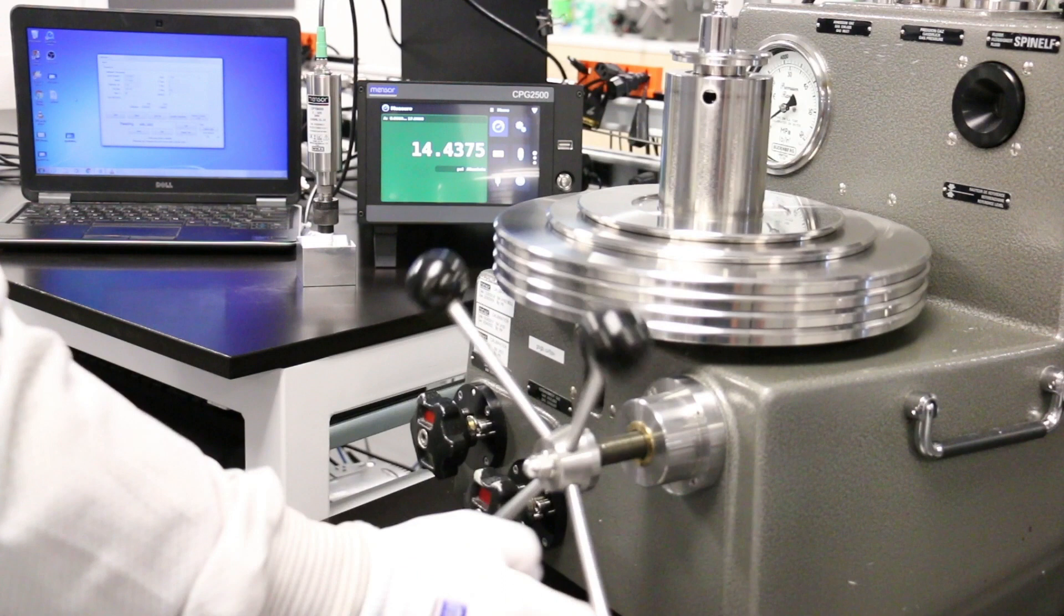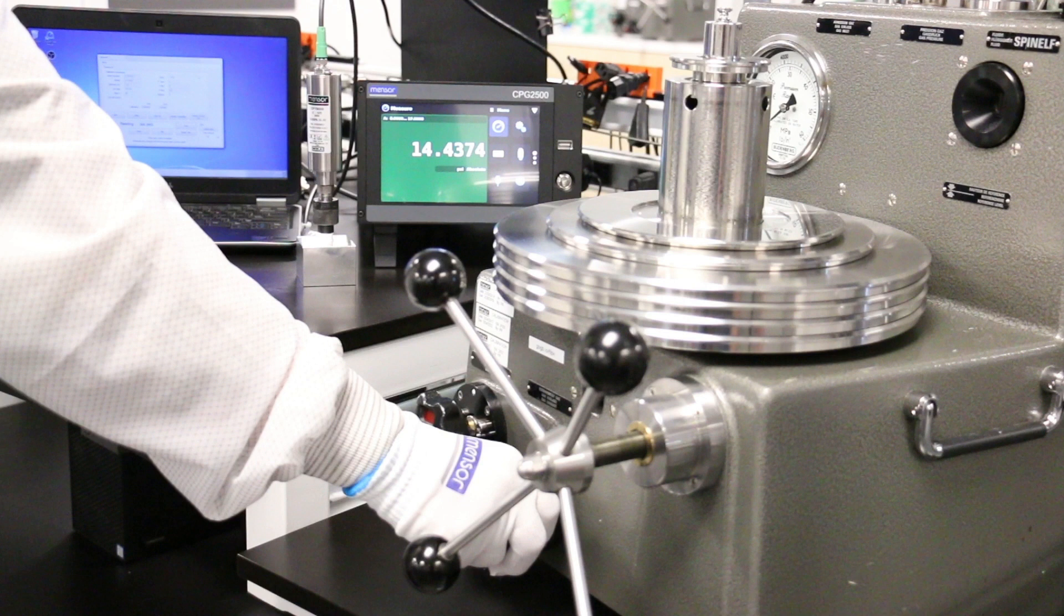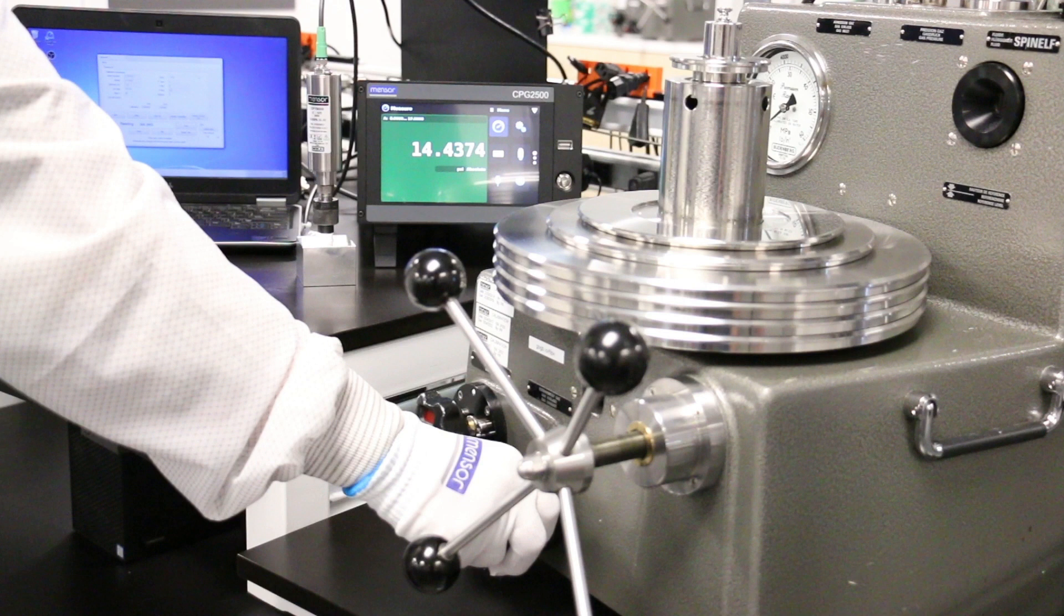Reduce the pressure back to the zero point and check it again. If it is out of tolerance, click the zero button, enter the reading from the barometer, then recheck the span to make sure it is in tolerance. Use the span button to make adjustment at span if needed. If all readings are in tolerance, you are done.